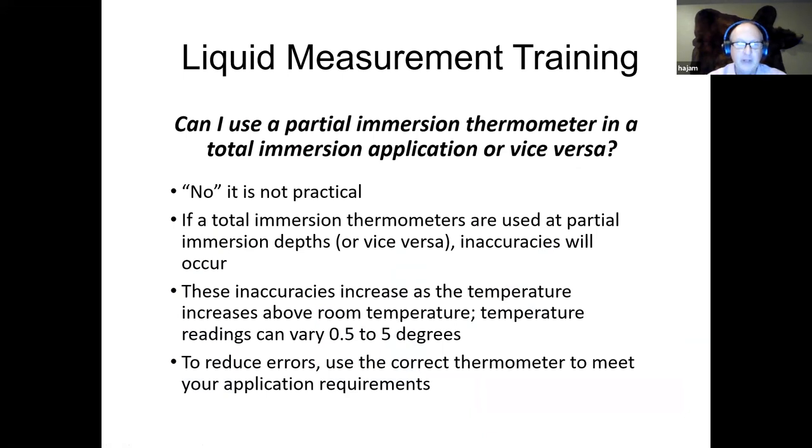A lot of times the thermometer is used incorrectly. I'll get asked a lot, can I use a partial immersion thermometer in a total immersion application, and a total immersion application is tank gauging, or vice versa? The answer to that is no, it's not practical. If a total immersion thermometer is used at partial immersion depths or vice versa, inaccuracies will occur.